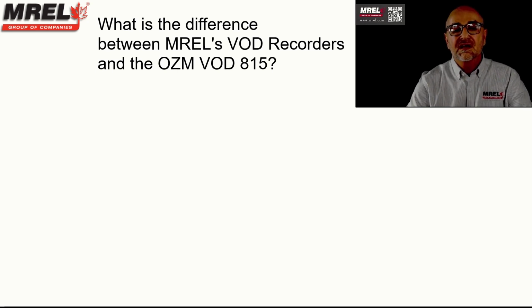The MREL VOD recorders can record a minimum of 200 data points per meter and up to 2,000 data points per meter of explosive in blast holes. This allows the change in VOD along the explosives column to be recorded easily.